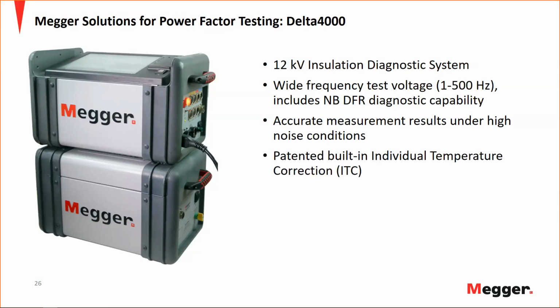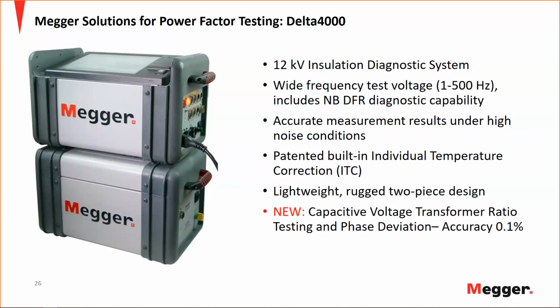The built-in patented individual temperature correction that I was talking about is required for evaluating 1 hertz properly, and is the only method that should be used for line frequency power factor correction, since the standards state that the tables are inaccurate and should not be used. The Delta comes in a lightweight 2-piece design, and we have also released some new accessories for the Delta, which will allow you to perform ratio testing on CCVTs.